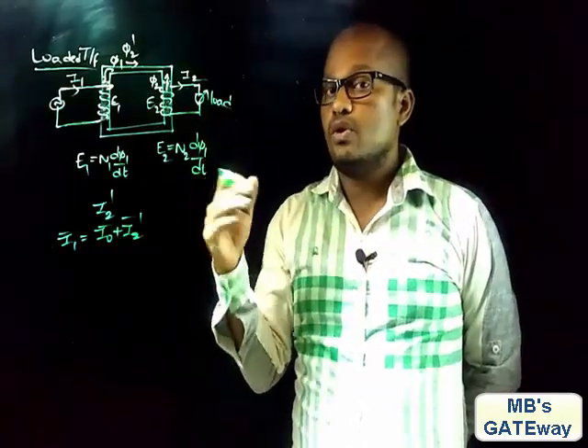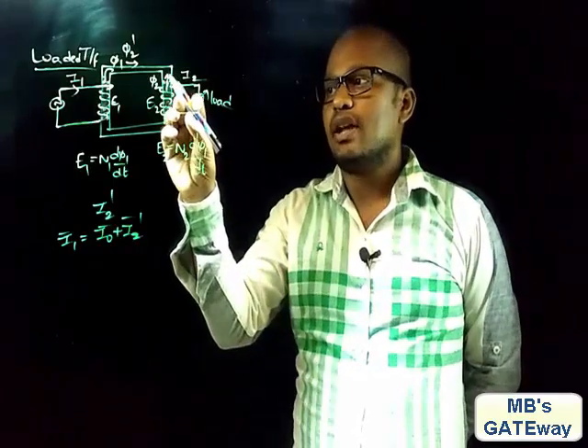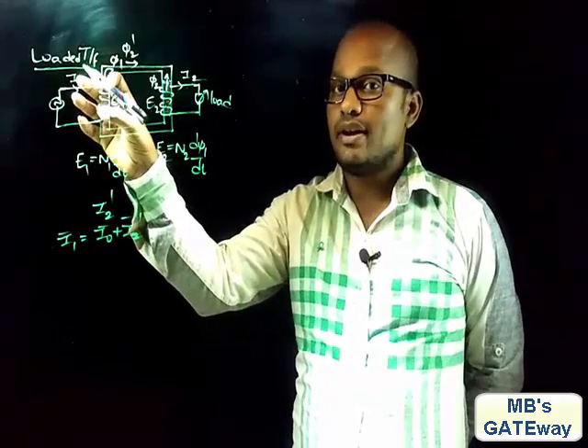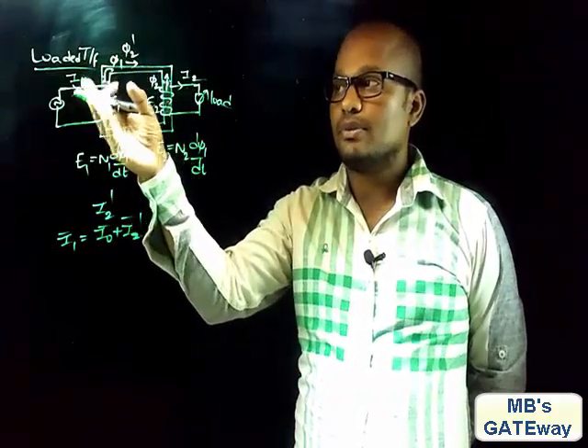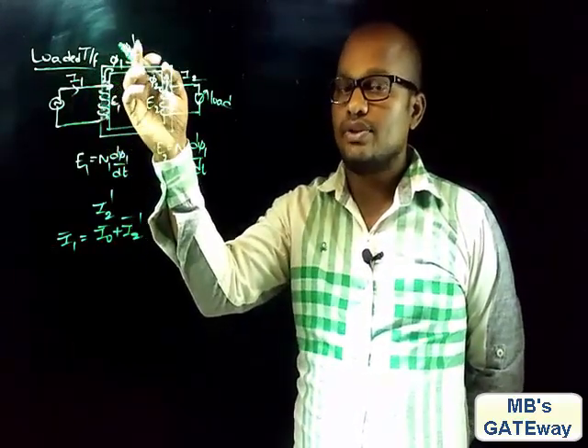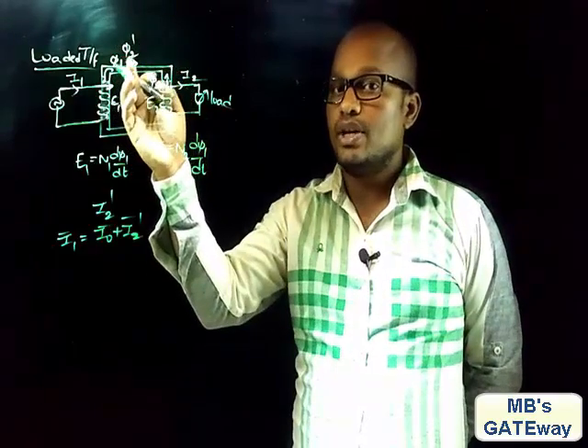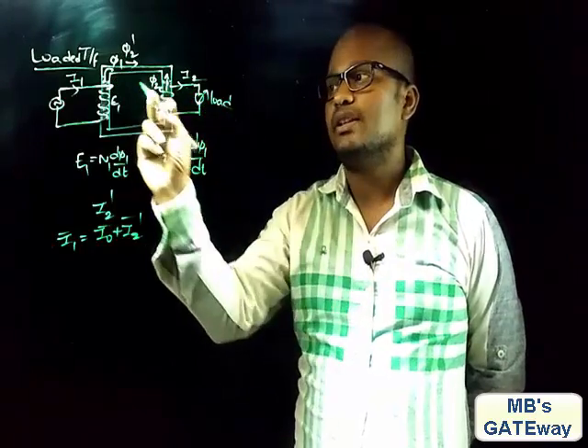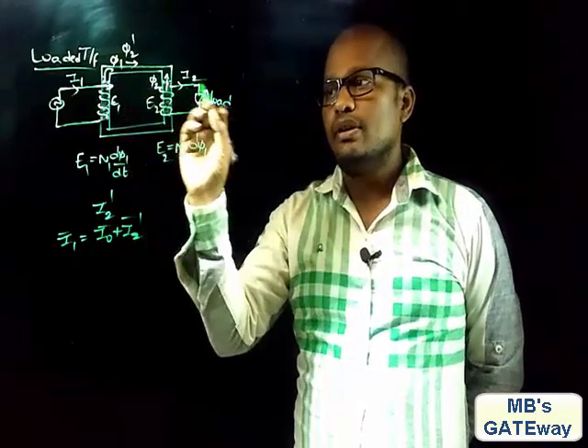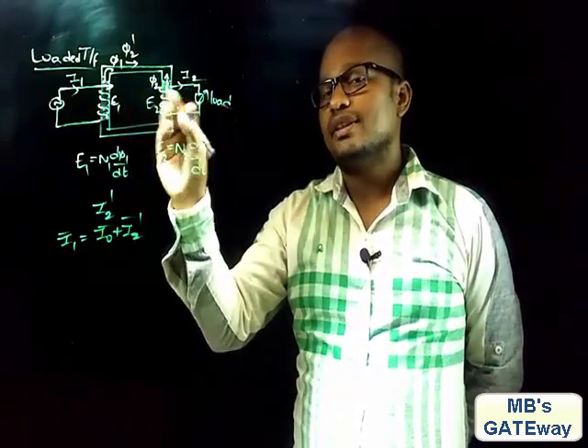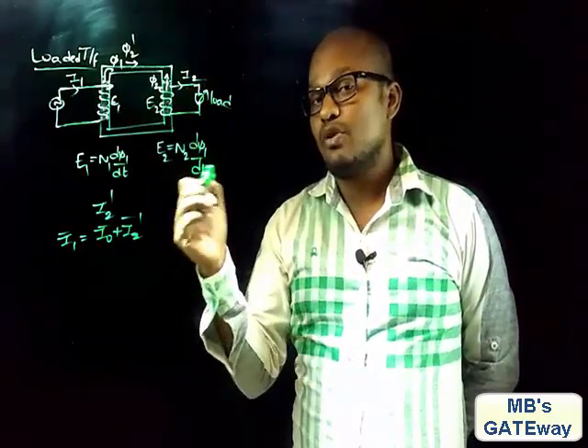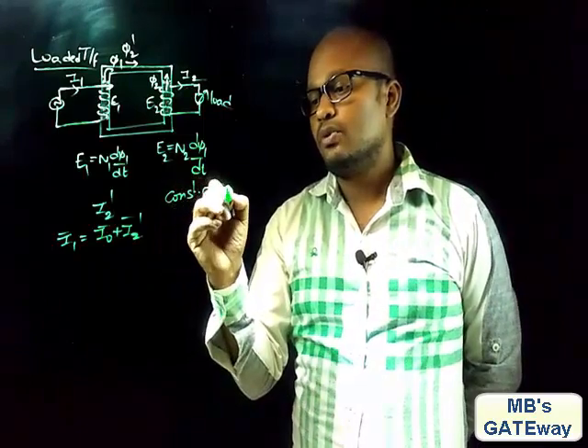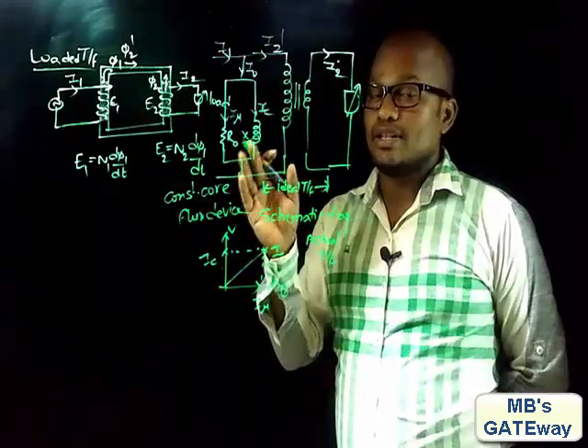So whatever load you place, a corresponding flux φ2 is produced, and accordingly the transformer draws extra current from the supply, generating φ2'. Since φ2 and φ2' are equal and opposite, they cancel, and the flux remaining in the core is always φ1. This is why the transformer is called a constant core flux device — irrespective of load, the flux in the transformer core remains constant.